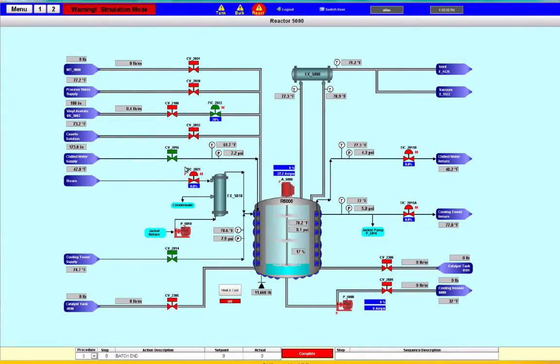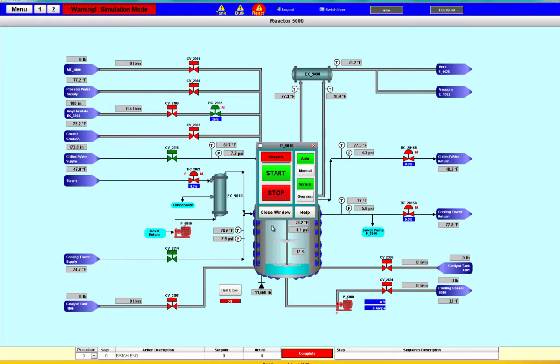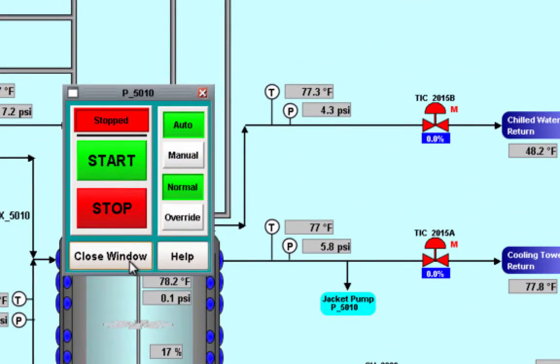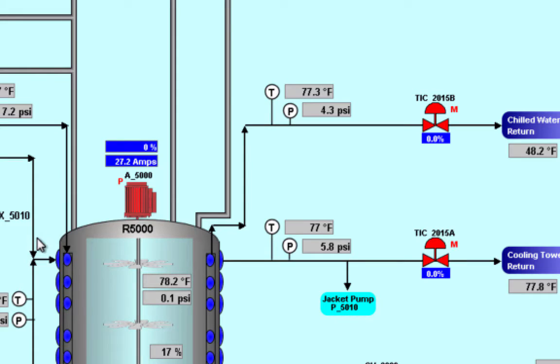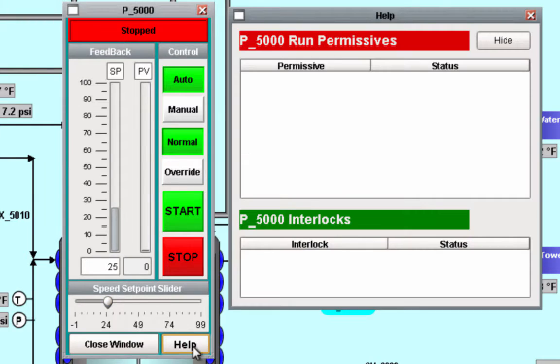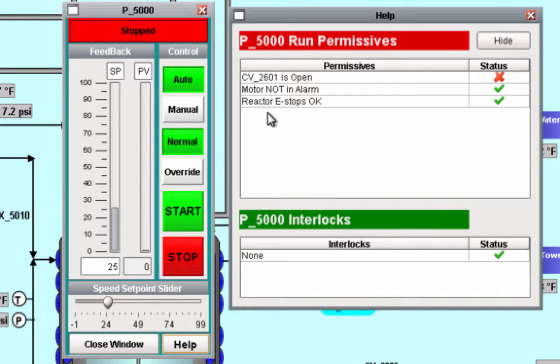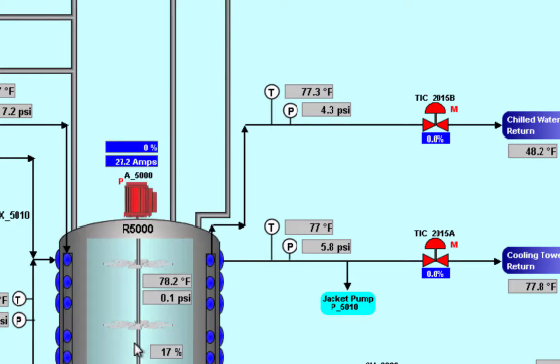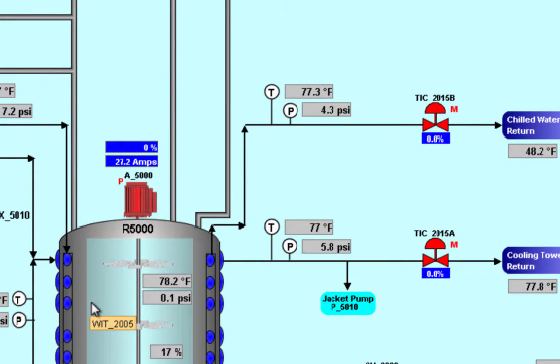Now while I'm proud of some of this, the capabilities to come in here and start and stop equipment and put it in manual and override it, such as for maintenance purposes — I think our permissive capabilities are really cool. You can see what permissives exist and what the status is. In other words, why will this not run? That little P down there says something's wrong and it's not going to run.